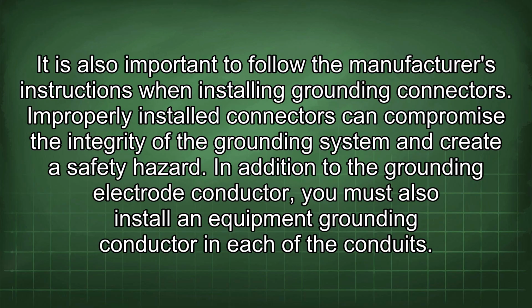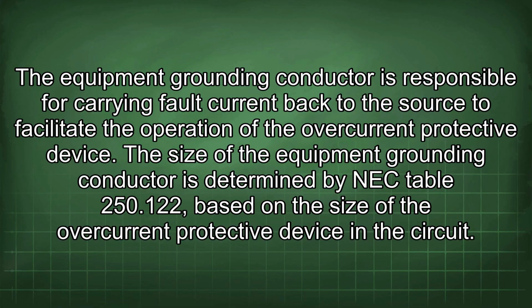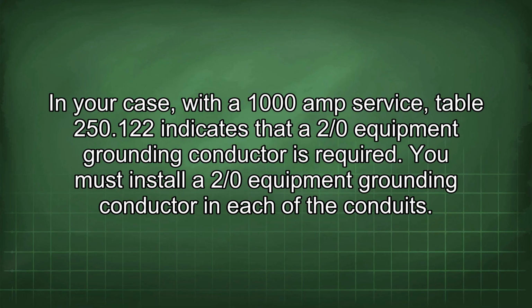In addition to the grounding electrode conductor, you must also install an equipment grounding conductor in each of the conduits. The equipment grounding conductor is responsible for carrying fault current back to the source to facilitate the operation of the overcurrent protective device. The size of the equipment grounding conductor is determined by NEC Table 250.122 based on the size of the overcurrent protective device in the circuit. In your case, with a 1000 amp service, Table 250.122 indicates that a 2/0 equipment grounding conductor is required. You must install a 2/0 equipment grounding conductor in each of the conduits.